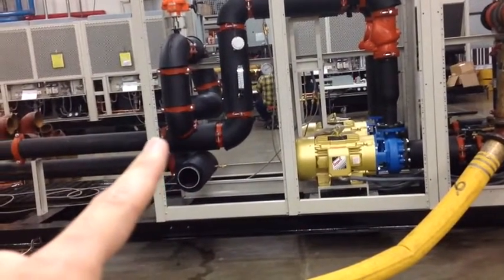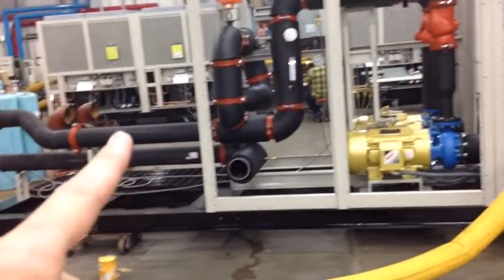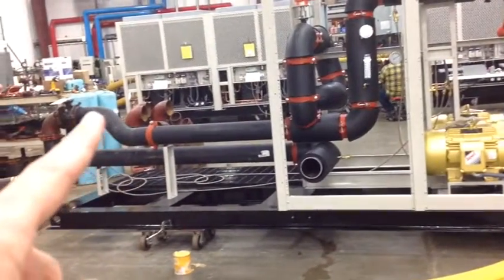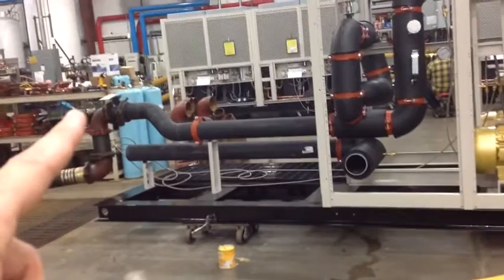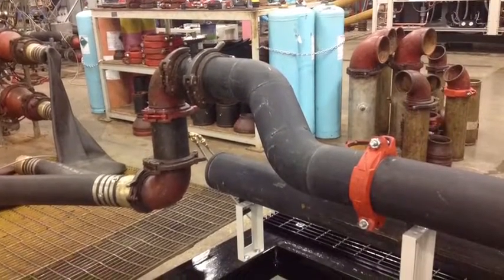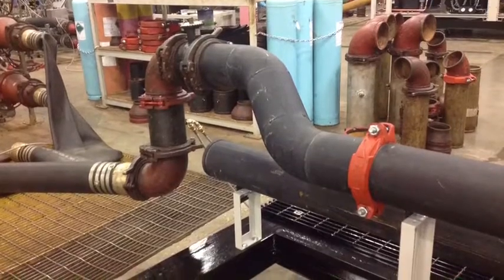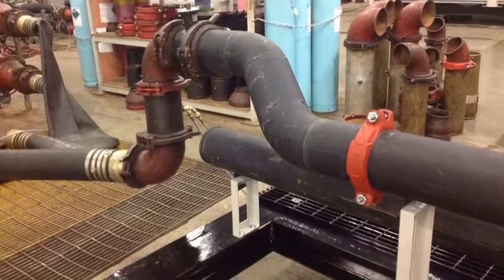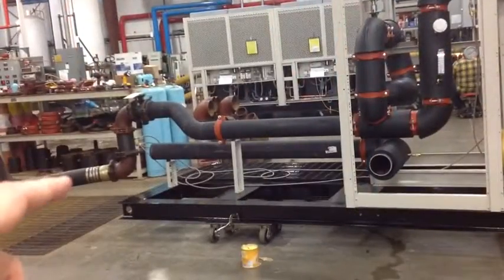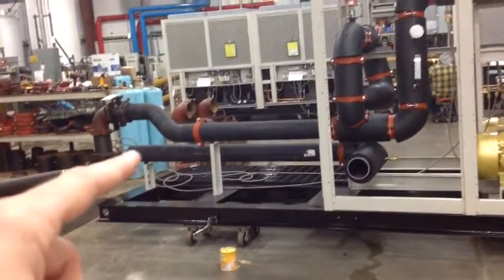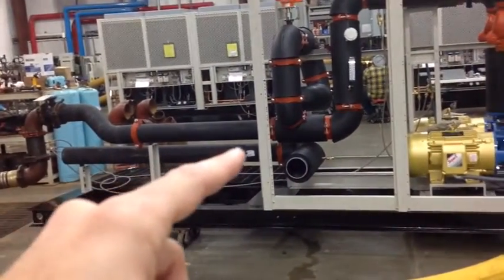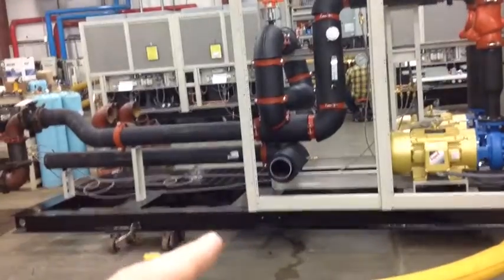You can also see the orange Belimo actuator at the top, which is the free cool bypass valve. The section that angles up that we just looked through is the portion where we adjust from where the free cool connection would be at the lower height to the mechanical entering height at a little bit higher elevation. Water comes back through the mechanical modules and exits the array here to go up into the building.